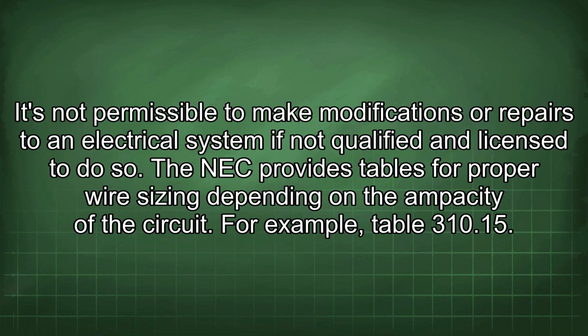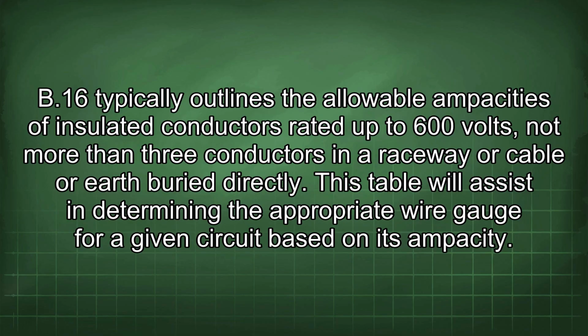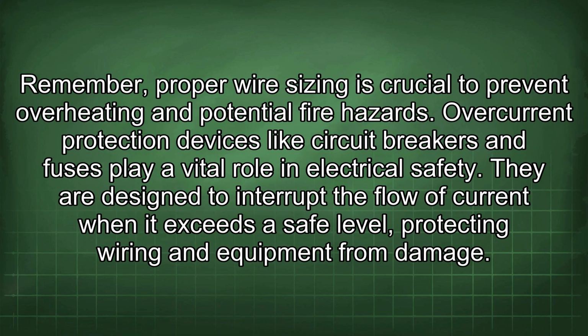For example, Table 310.15(B)(16) typically outlines the allowable ampacities of insulated conductors rated up to 600 volts, not more than 3 conductors in a raceway or cable or earth buried directly. This table will assist in determining the appropriate wire gauge for a given circuit based on its ampacity. Remember, proper wire sizing is crucial to prevent overheating and potential fire hazards.